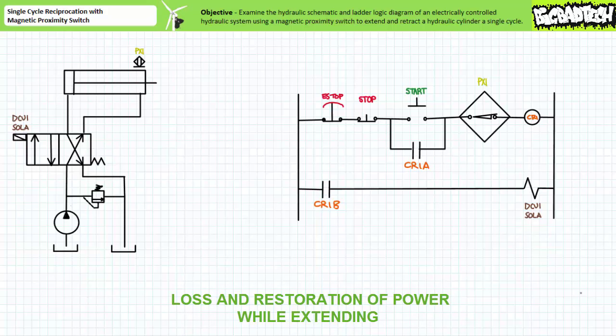Note that this single cycle reciprocation circuit featuring the magnetic proximity switch, as well as our previous one featuring the physical limit switch, both exhibit low or no voltage protection characteristics. Consider the behavior of three-wire control systems during an unexpected power outage. If the system was in the act of extending and experienced a sudden loss of pilot power, the coil of CR1 would be de-energized and all associated contacts CR1A and CR1B would return to their deactivated open state. When CR1A opens it removes the holding circuit. When CR1B opens, DCV1 Sol A is de-energized and DCV1 returns to the spring offset cross-connect position. If primary hydraulic power was still present the cylinder would retract; if also lost, the cylinder would stall in position.